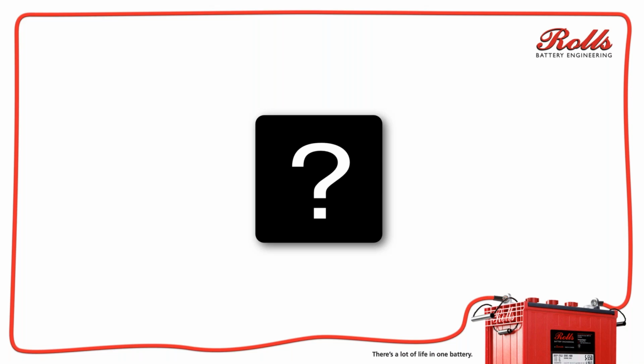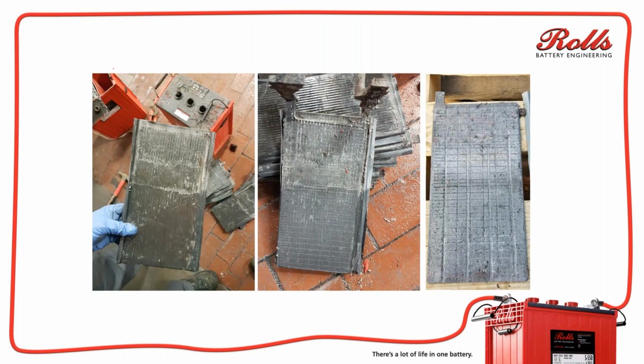And so what that looks like is this here is when you underfill a battery. Gotta wait for my computer, or my internet connection, to catch up. As soon as it catches up. So what ends up happening is that you expose the plates to air, and that air causes corrosion, and that corrosion is going to cause problems with the battery bank in general.